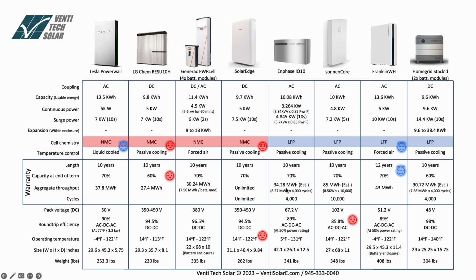Enphase, 34.28 megawatt hours estimated. Basically, they don't give you an aggregate throughput in megawatt hours. They just tell you how many cycles are expected out of it. And if you have the cycles, the number of years and the percentage that your battery is supposed to be at the end of the cycles, you can calculate the aggregate throughput. So that's what we did here. 8.57 times 4,000 cycles gives you that 34.28 megawatt hour estimated throughput.